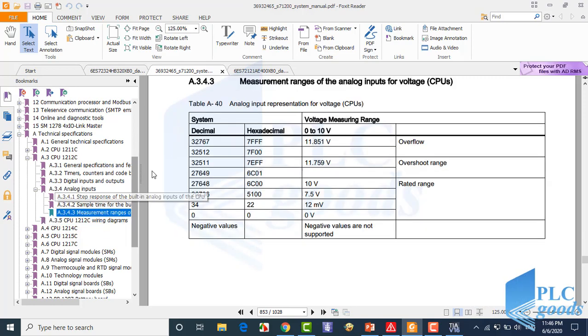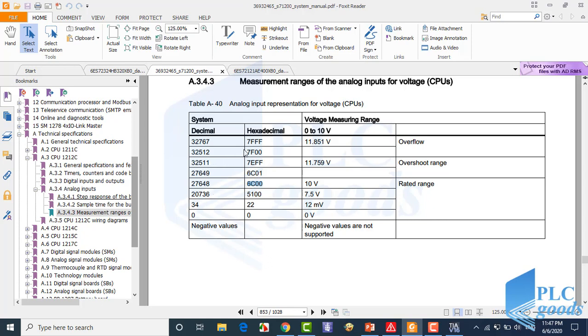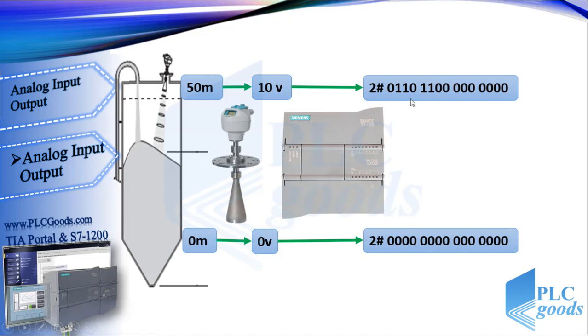Now pay attention to this table which shows the measurement ranges of the analog inputs for voltage signals. Based on this table, negative values are not supported. For zero voltage my CPU gives me zero, and for 10 volt it gives me the hexadecimal number 6C00, which is equivalent to 27648. So we'll have these numbers respectively for 0 to 10 volt at the PLC input.